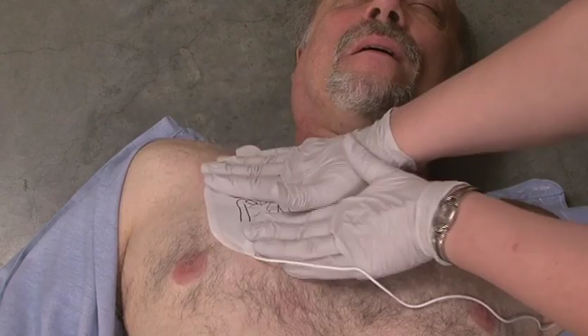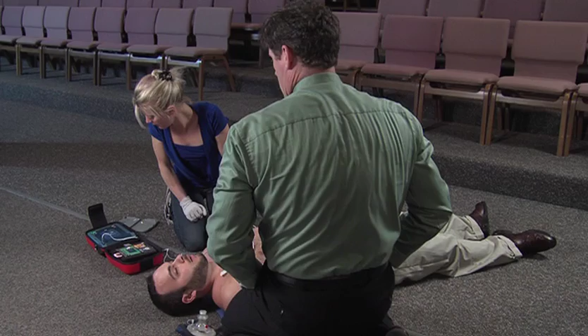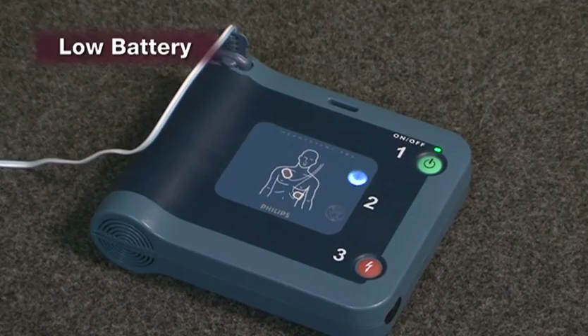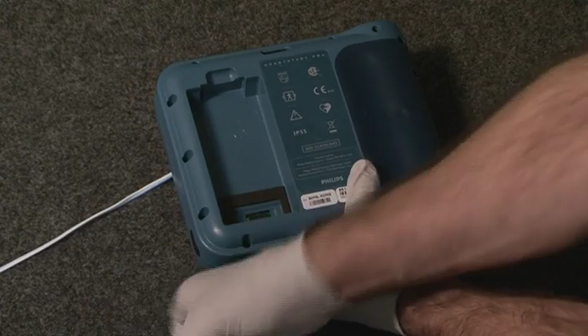Another troubleshooting message may indicate that analysis has been interrupted due to movement. Stop all sources of movement, such as chest compressions or rescue breaths. If a message indicates the need to replace a battery, there may only be enough energy for a limited number of shocks. If the AED fails to operate, the depleted battery should be removed and replaced with a new one.